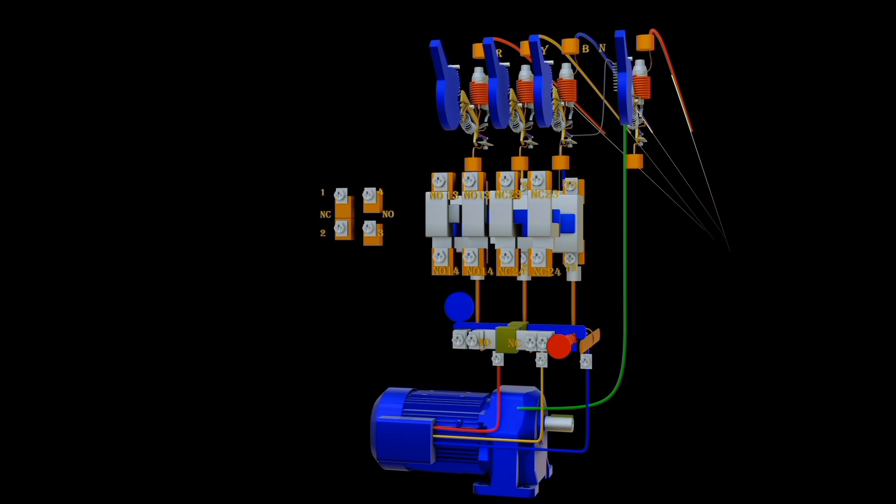Then, the control wire conductor connected from the single-pole circuit breaker passes through overload relay normally closed contacts, then to the normally closed contacts of push button, that is stop push button terminal 1.